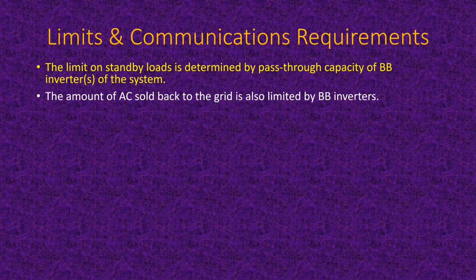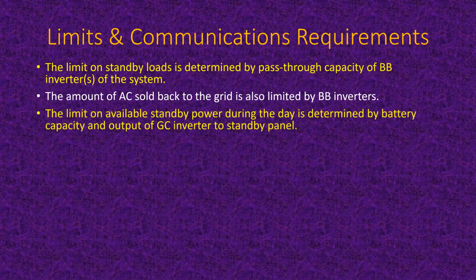Okay. The amount of AC sold back to the grid is limited by the battery backup inverters, because it's either a matter of how much they'll pass through from the other, or if the batteries are turning on and you're selling back to the grid from your batteries, that's another story. There's two different cases. You could be selling battery power back to the utility, and that's limited by that inverter. Or you could be selling PV power back through an AC coupled system. Then your battery backup inverter simply has to have enough pass-through capability to pass through the entire output of the grid connected non-backup type inverter in that AC coupled system. Okay, so things to think about.